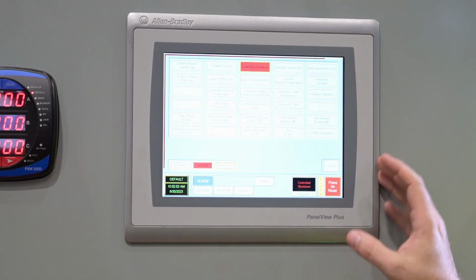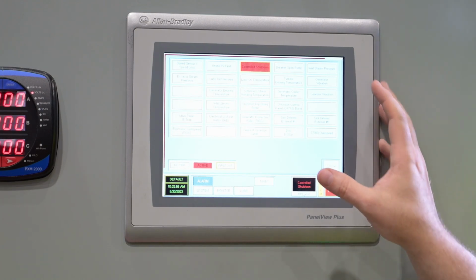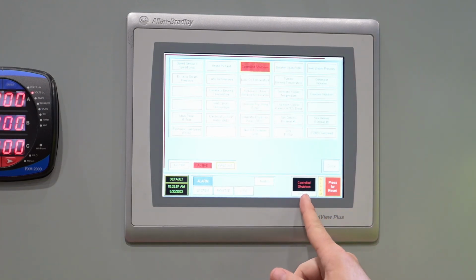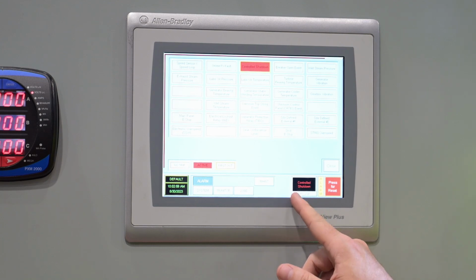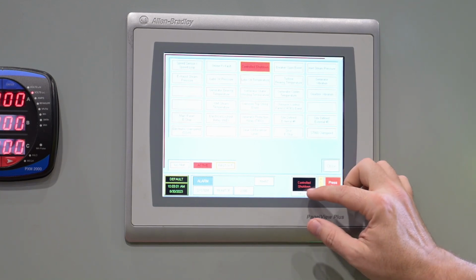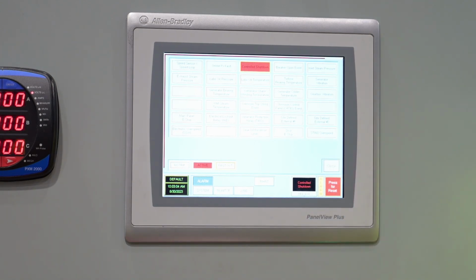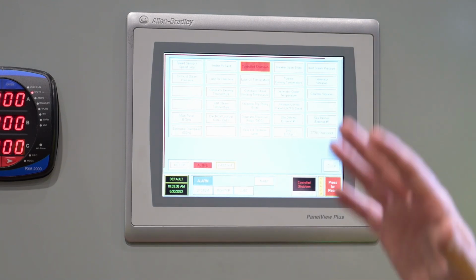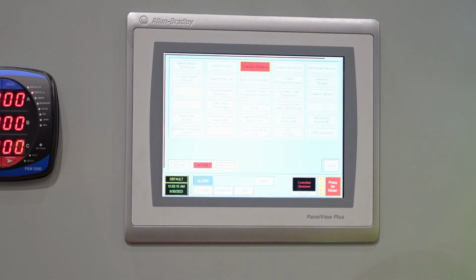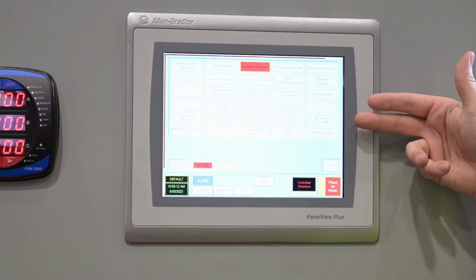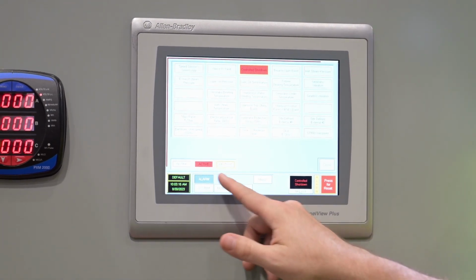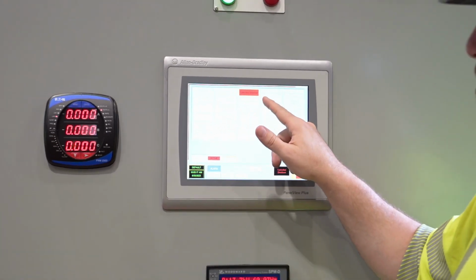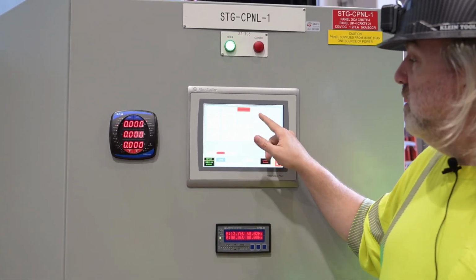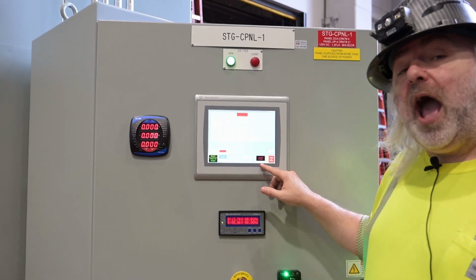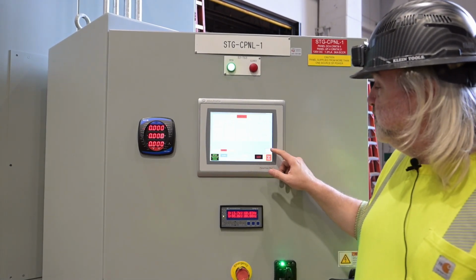In addition to the alarm screens, the other alarm and trip indication is our first out screen. On the first out, we have an indication of what that first out was. First out means when the system was running and then the system tripped, that was the cause of the trip. There could be additional trips, but what we're focused on is the yellow. The controlled shutdown, in this case, was our last trip. We can also see that on the first out button itself.